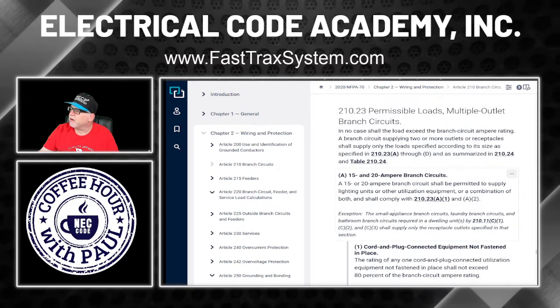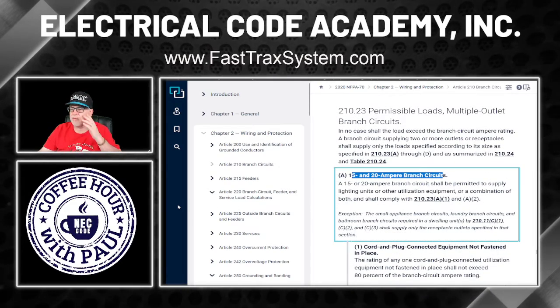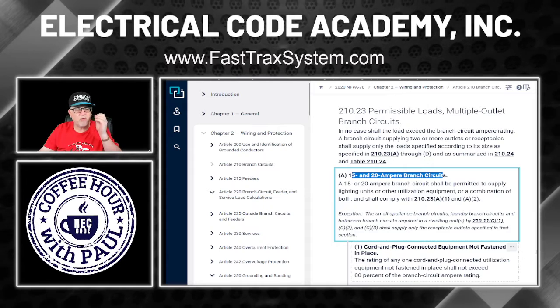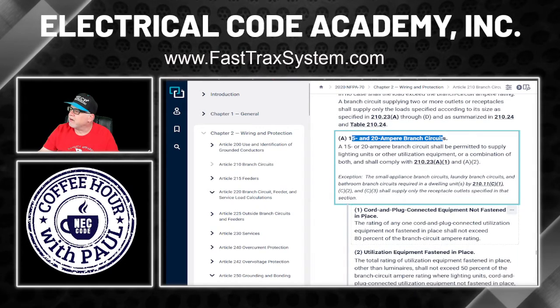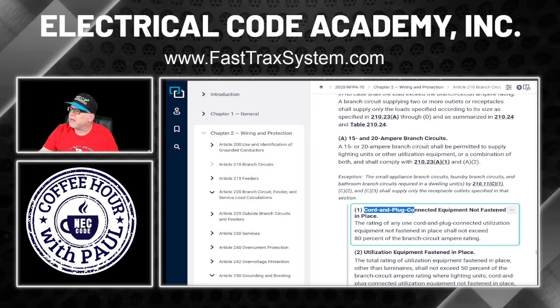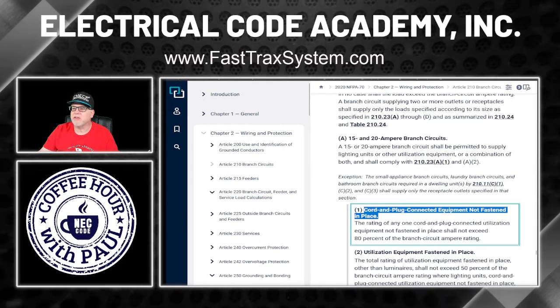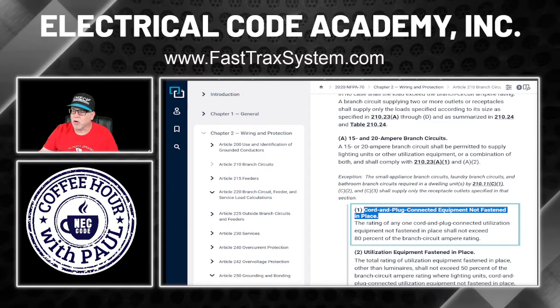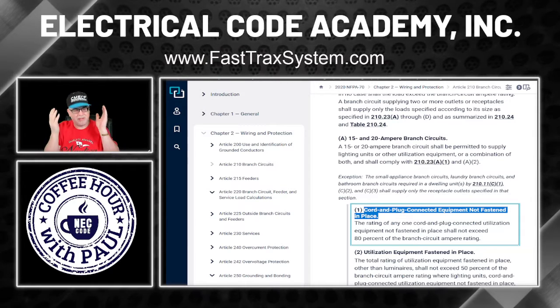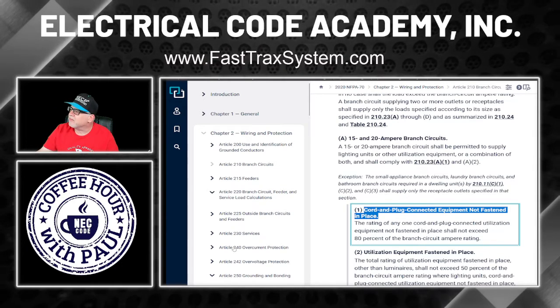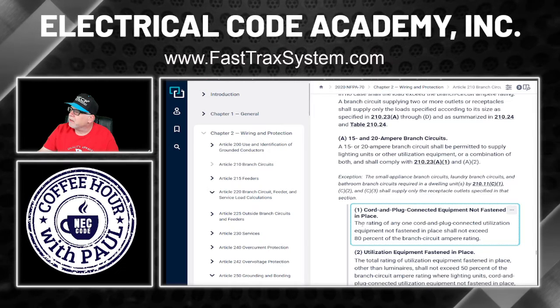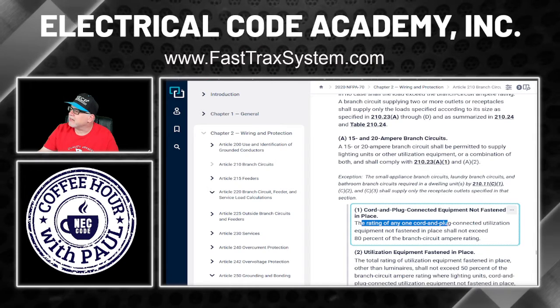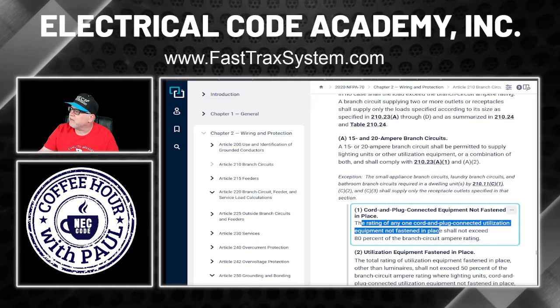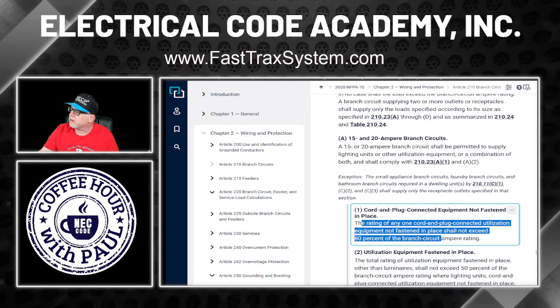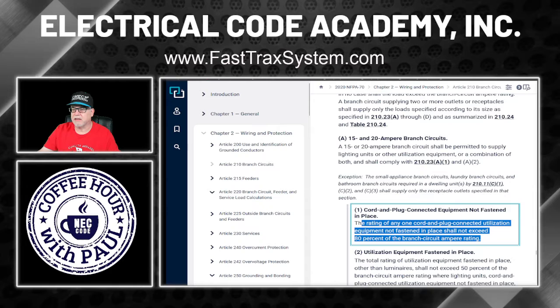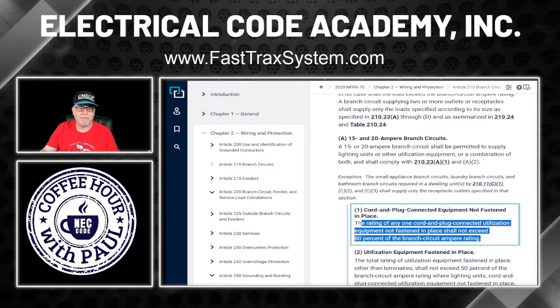Okay, what do you see here? 15 and 20 amp circuit. This was a 20 amp circuit. Remember we said reason for writing these things down? Right here: cord and plug connected equipment not fastened in place. All right, so this says any one cord and plug portable. Okay, so it's obviously not fastened in place. It says the rating of any one cord and plug connected utilization equipment not fastened in place shall not exceed 80% of the branch circuit's rated amperes. Okay, so we were ready to click this 20.